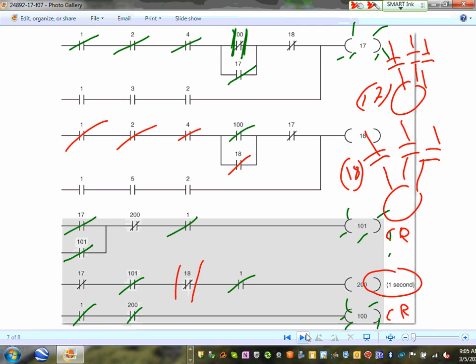We call this an off-delay timer. You energize the relay — the timer starts. When you de-energize the timer, it waits, say, two seconds — if you set it to two seconds — before it opens the contacts. That's basically what you can do.